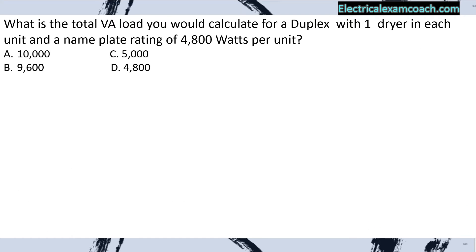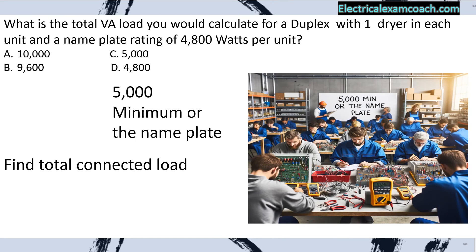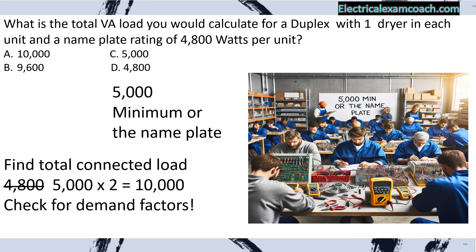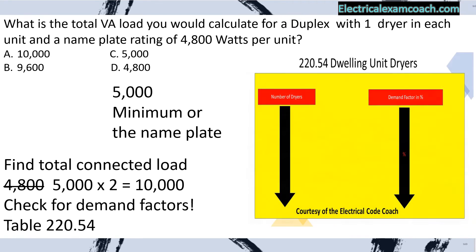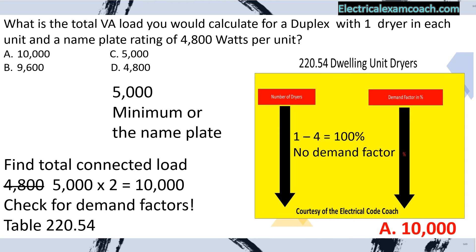What is the total VA load for a duplex with one dryer in each unit and a nameplate rating of 4,800 watts per unit? We apply the 5,000 VA minimum, so the 4,800 is out and 5,000 is in. We multiply by our two units, giving us 10,000 VAs total connected load. Checking table 220.54, one through four dryers is calculated at 100%. Answer: A.